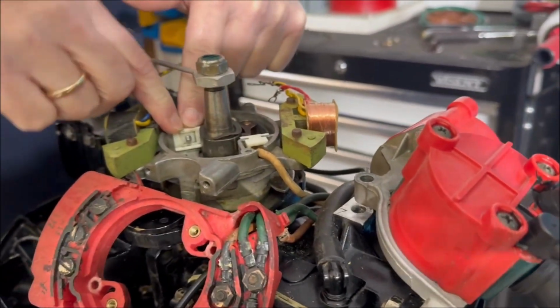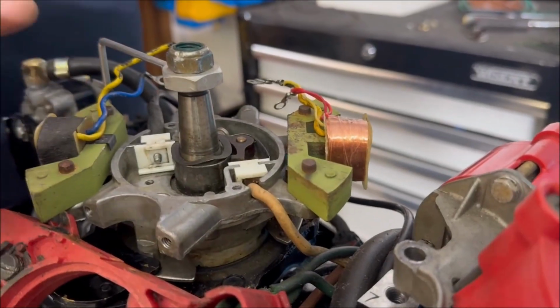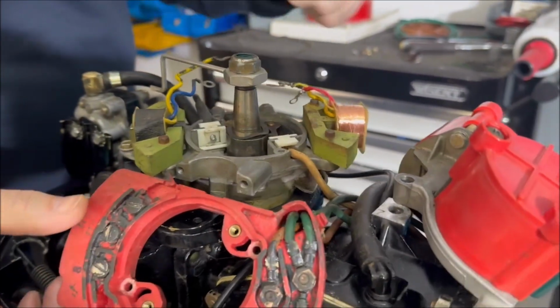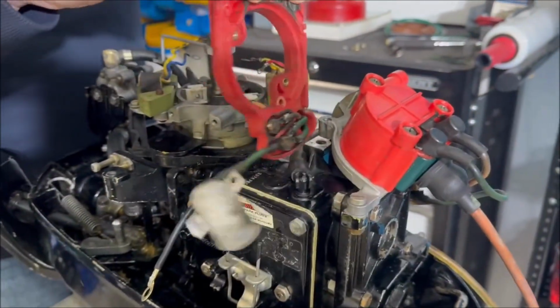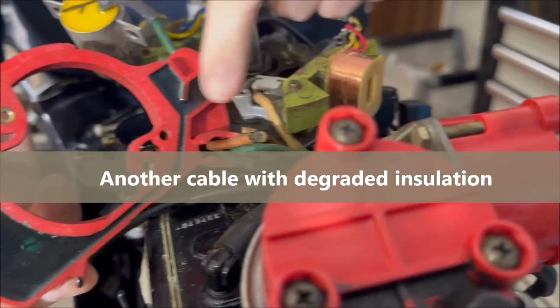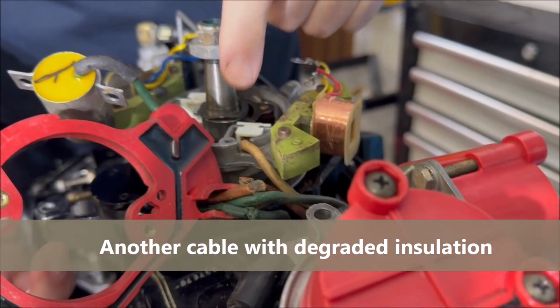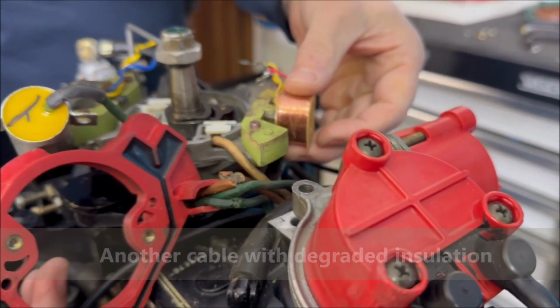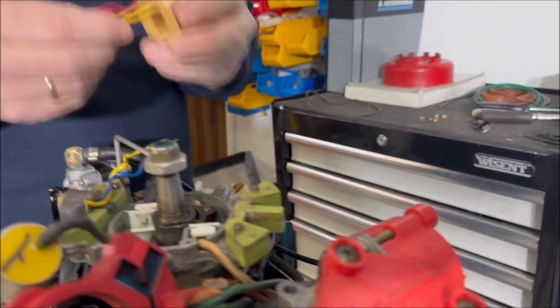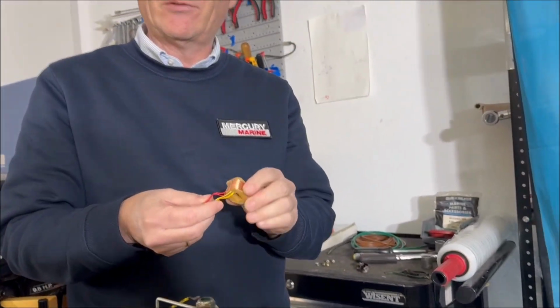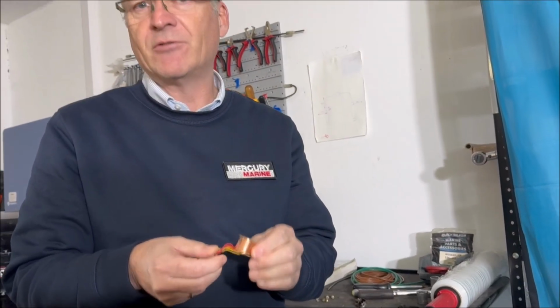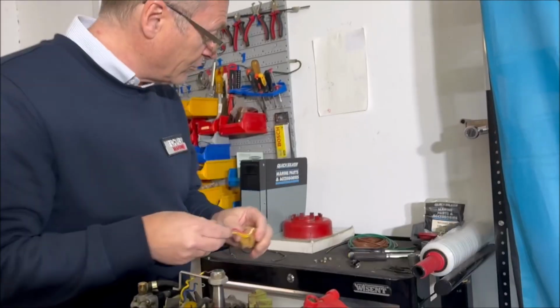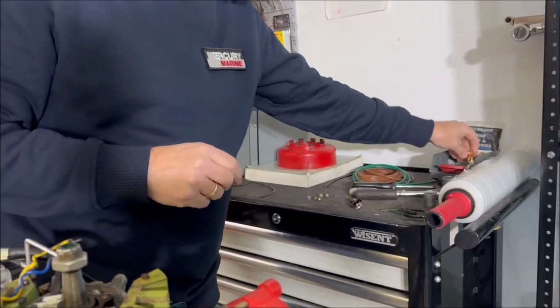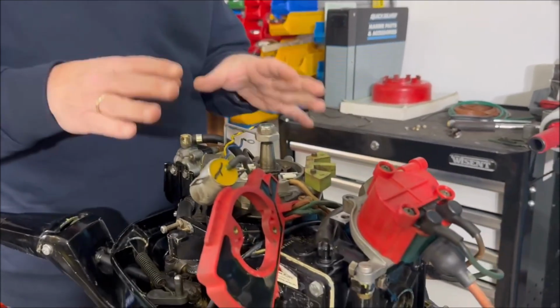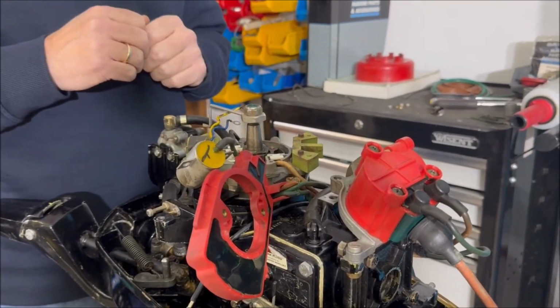As you can see, we did some cleaning, so we're ready to put the breakers in again. What we also need to look at is all these cables are all broken, so we need to replace these ones. I also had a look at the coil, and the coil doesn't have the right resistance, so it has to be replaced. We're going to look at that next time. So now we're going to do the cables and find a new coil for it.